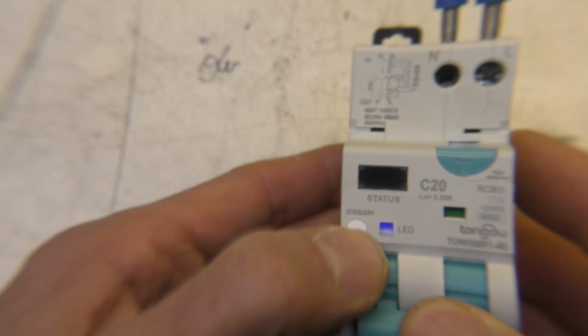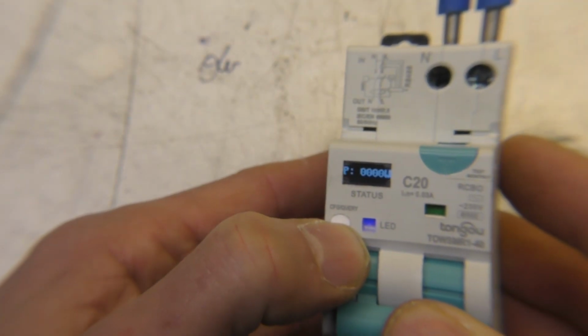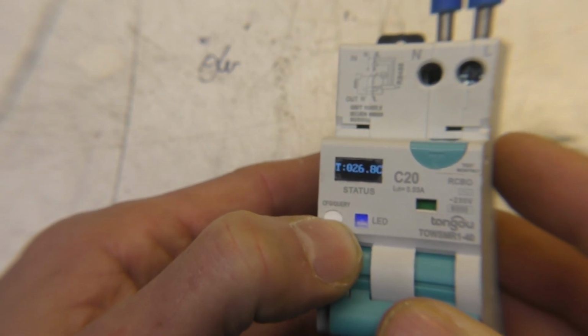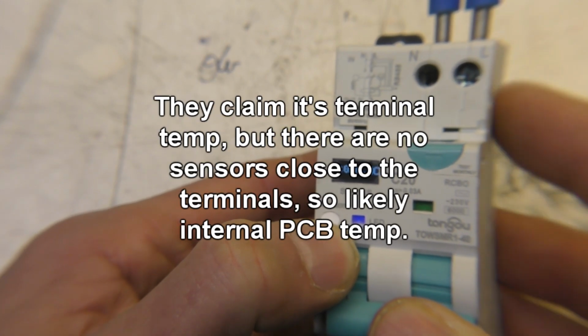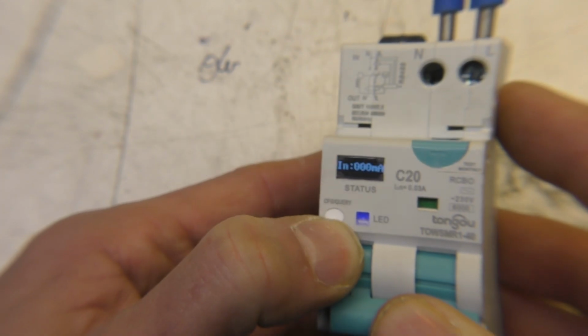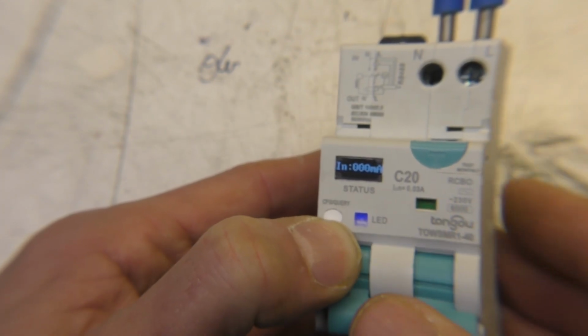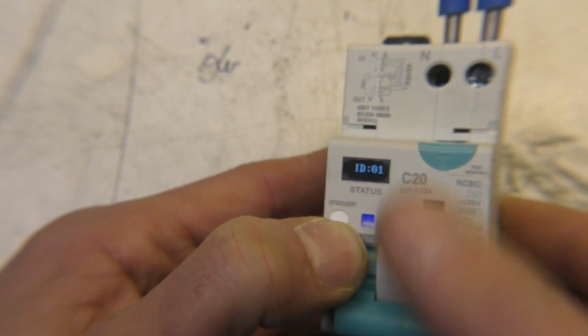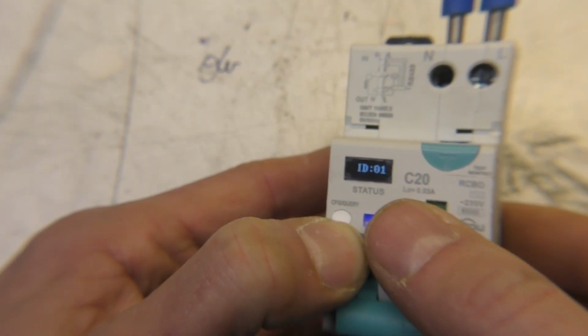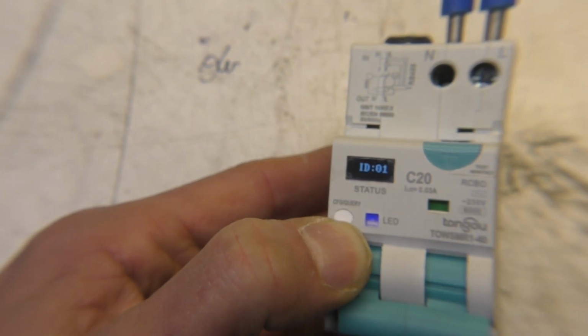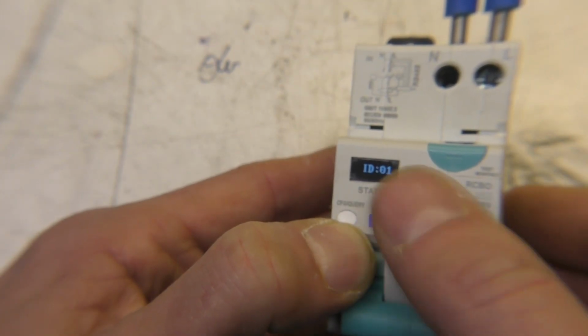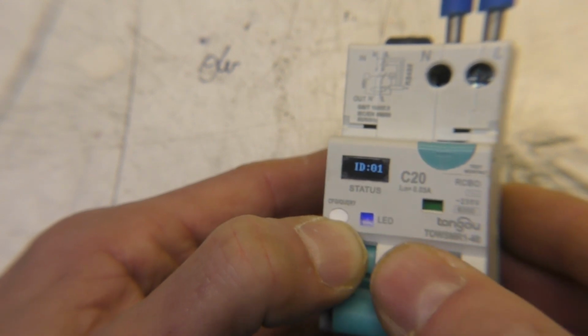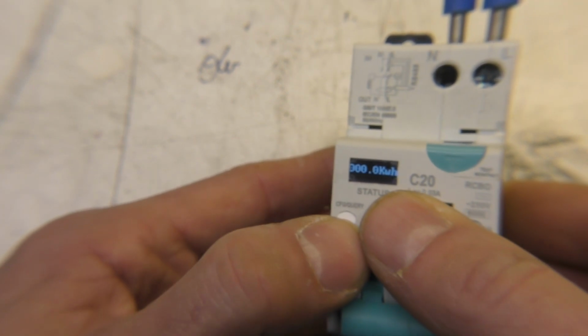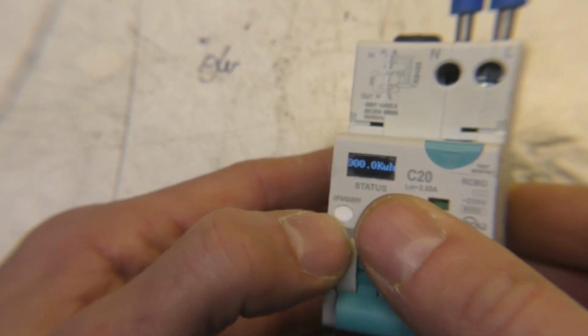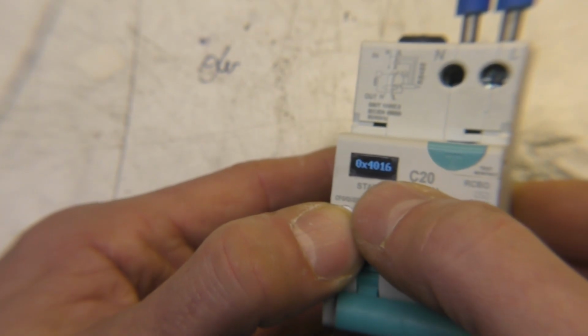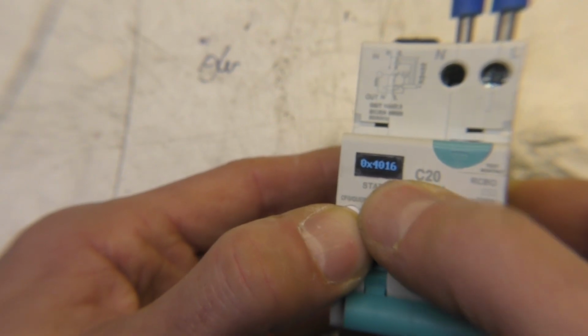Base settings, voltage, current, power, temperature, and I think this is actually the temperature of the terminal, so you can detect if there's a bad connection causing overheating. Earth leakage current, which could be quite useful for doing diagnostics. There's an ID. I haven't figured out any way to set this. I'd imagine the idea is that you can set different breakers in a cabinet to different IDs, but I haven't immediately found any way to set that. Kilowatt hours, I'm not sure how you reset that, but again, sort of running total of energy. That, I've no idea what that is. That could just be a software version number or something. I haven't found any reference to that in the documentation.